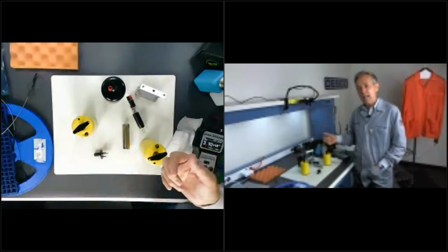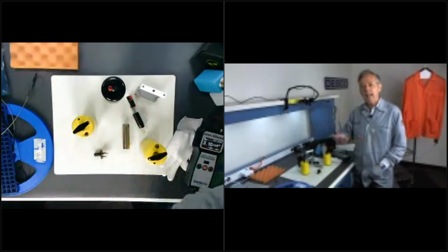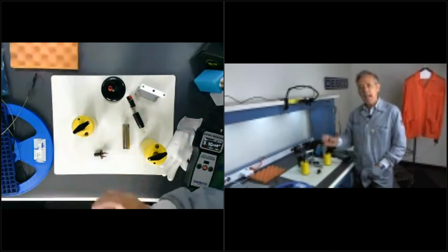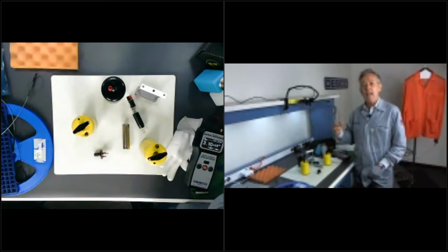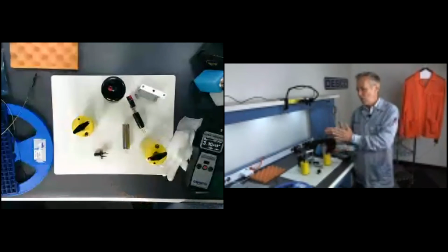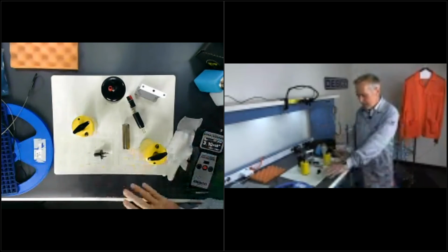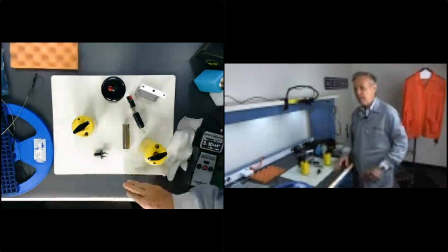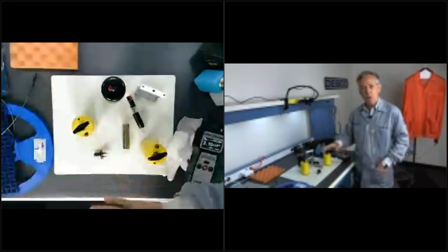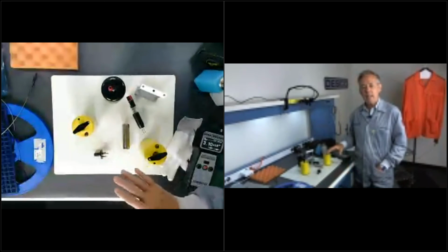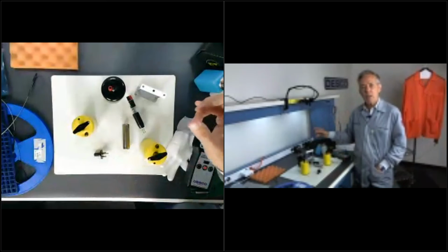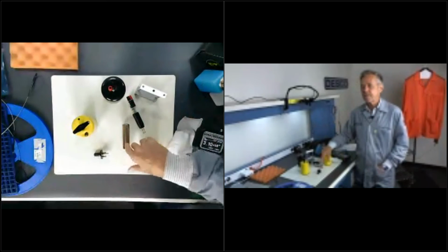If it's out of spec, then I go back and clean that surface, then retest, because I want to make sure that it's not the contamination that's causing the problem. So you always test real world first, and if that fails, I might check to see if my ground cord is still attached, and check my surface resistance. I might then clean the surface, whether it's a floor or work surface, to make sure that's not the problem. But I always start with RTG first.